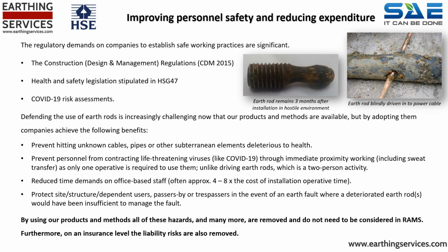From our discussions with several HSE inspectors following either utility strikes or other RIDDOR reportable incidents associated with earth rods, we have captured this summary. Their chief concerns relating to earth rods amount to the risks of hitting subsurface elements, particularly utilities, the hazards associated with the physical installation, and the ongoing reliance on a safety measure that may have become insufficient through deterioration.